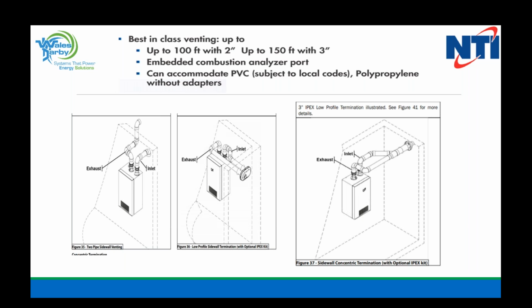We recently did a class a couple of days ago that Anthony Tassi did on condensing boilers and hydronic systems. He did an excellent job showing the importance of using the right materials for venting and making sure that your flue gas temperatures are within the range of that venting material. So PVC, even though it's inexpensive, is generally not the best for venting. Though we can use it, you must stay within the guidelines of the temperature rating for that product. So polypropylene is really your best option.